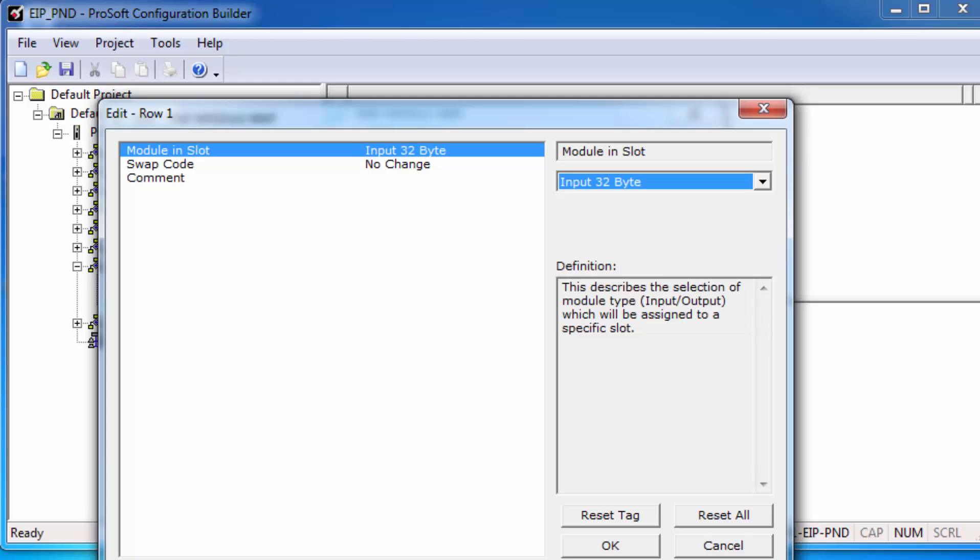Just click on Module in Slot and from the drop-down list choose Input 32 bytes. If you notice your bytes or words are scrambled, you might need to swap bytes or words for this particular module, and we can do that by using the swap code here.